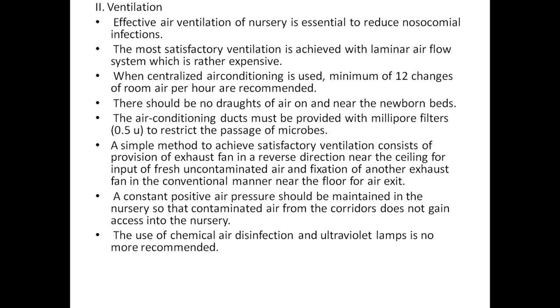A simple method to achieve satisfactory ventilation consists of provision of an exhaust fan in a reverse direction near the ceiling for input of fresh uncontaminated air, and fixation of another exhaust fan in the conventional manner near the floor for the air exit. A constant positive pressure should be maintained in the nursery so that contaminated air from corridors does not gain access into the nursery. The use of chemical air disinfection and ultraviolet lamps is no more recommended.